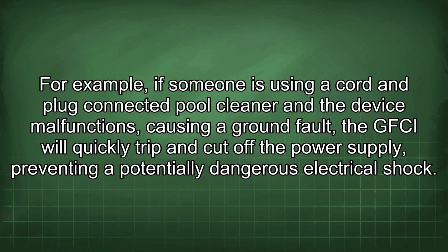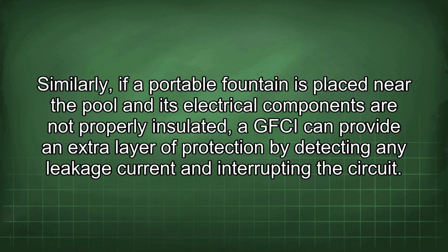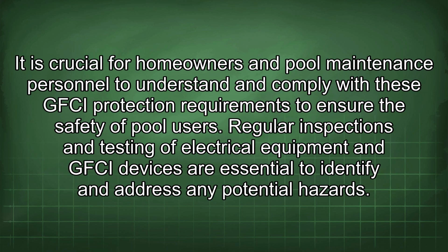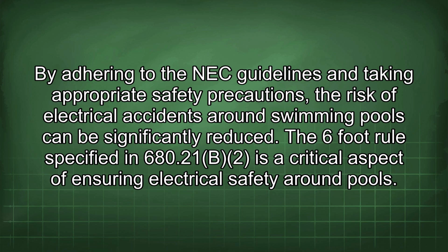For example, if someone is using a cord and plug-connected pool cleaner and the device malfunctions, causing a ground fault, the GFCI will quickly trip and cut off the power supply, preventing a potentially dangerous electrical shock. Similarly, if a portable fountain is placed near the pool and its electrical components are not properly insulated, a GFCI can provide an extra layer of protection by detecting any leakage current and interrupting the circuit. It is crucial for homeowners and pool maintenance personnel to understand and comply with these GFCI protection requirements to ensure the safety of pool users. Regular inspections and testing of electrical equipment and GFCI devices are essential to identify and address any potential hazards. By adhering to the NEC guidelines and taking appropriate safety precautions, the risk of electrical accidents around swimming pools can be significantly reduced.